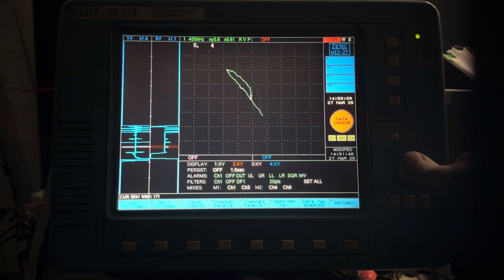So let's go to our 60, which will be our next one. That's about the same. That's because the diameter of the 60 is a little bit larger than the 80. And the purpose of that is to make the signal size the same. So 100, 80, 60 are all about the same amplitude, because there's the same amount of metal missing from each one of those machined flaws.